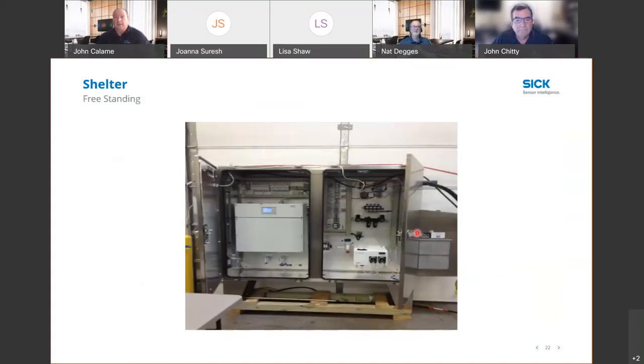So you have freestanding enclosures that you can close the doors on, and they protect the analyzers and the sample system itself. Then you have to come out and open the door. Sometimes I've seen the freestanding ones, especially on the Gulf Coast, have to meet hurricane specifications: withstand a certain amount of wind force, shear force, and in some areas where they expect tidal surges, they may be up on platforms a certain distance above the ground clearance.